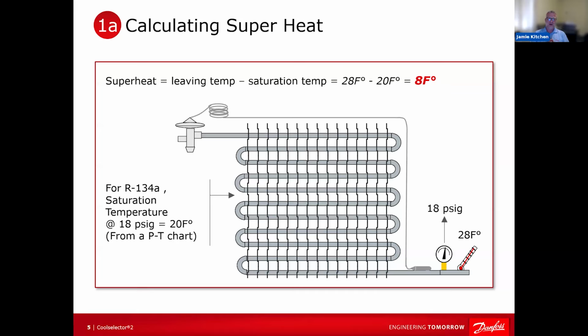And then once we run out of liquid, that 20-degree refrigerant, 100% vapor, is going to start to warm up and superheat. If you want to know what a superheated vapor looks like, look around you. The atmosphere is superheated. Steam, when it's superheated, is clear. Gases like refrigerant are clear when they're superheated. So if you see steam, it is not superheated. If you can see it, it's not superheated. Very interesting. And the big thing is that you need to know how to do this. This is a check that is overlooked and missed.